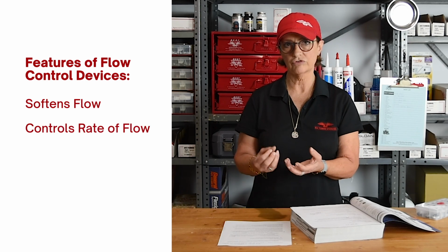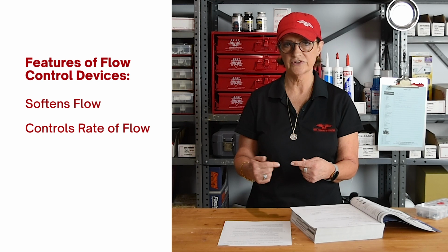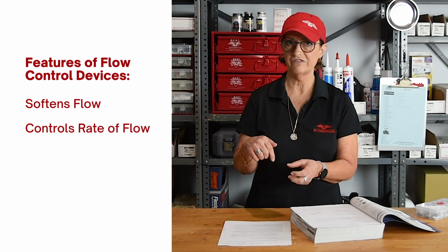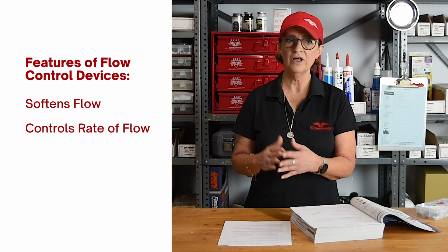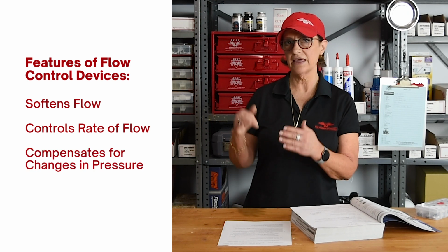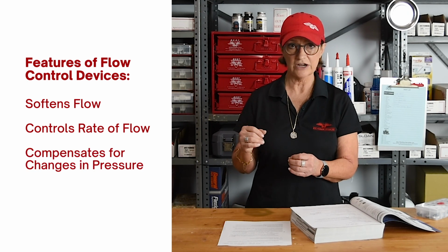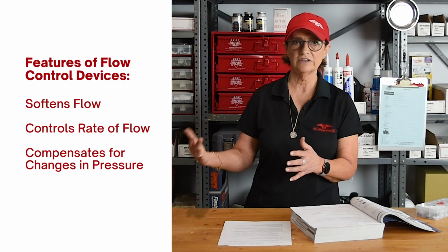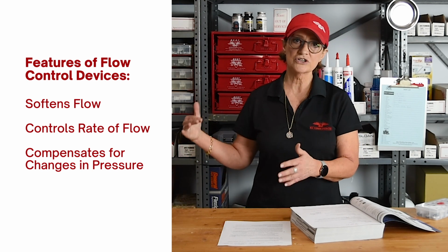It also controls the rate of flow, so the gallons per minute that comes out of that faucet. They also control the pressure. They compensate for changes in pressure because the water coming into a building from the street, the pressure fluctuates. That's why they have systems and pumps and things to accommodate for that. But at the very end, at the point of use, there is still a pressure compensator, and that is what we call aerator, which is actually the flow control device.